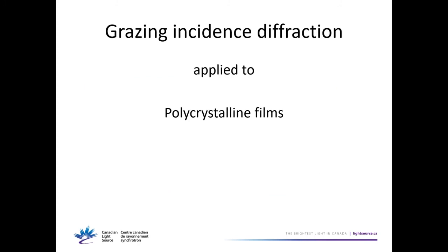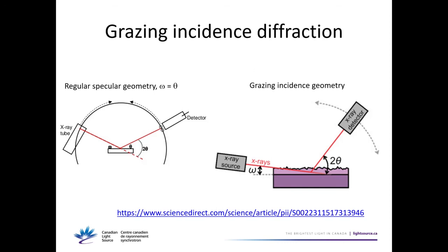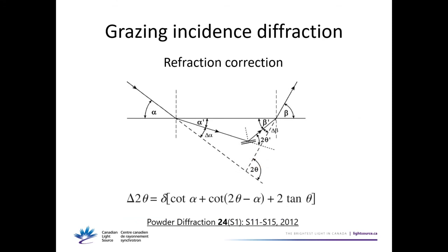In the regular specular geometry, omega — the incidence angle — equals theta. For grazing incidence diffraction applied to polycrystalline films, the incidence angle is kept grazing while the detector moves to scan two-theta. Grazing incidence requires several corrections: absorption correction, Lorentz polarization factor correction, atomic scattering factor, and particularly a refraction correction that becomes more important the more grazing the incidence angle is.